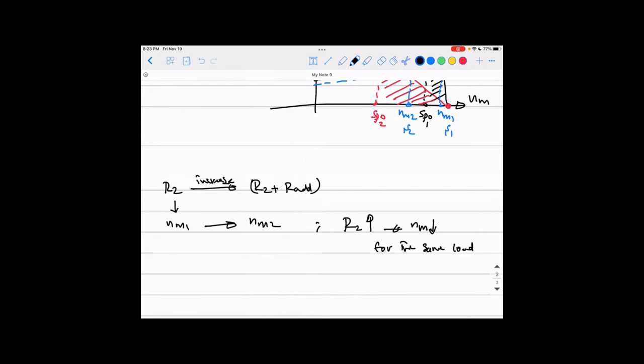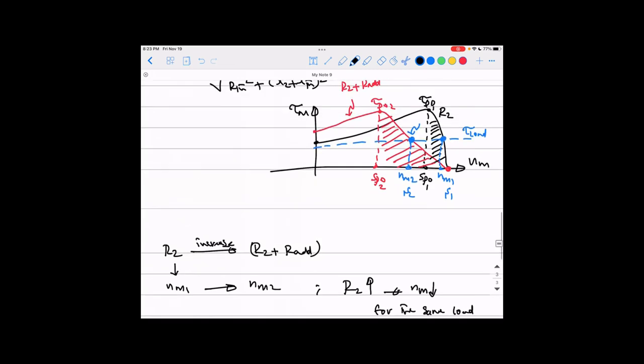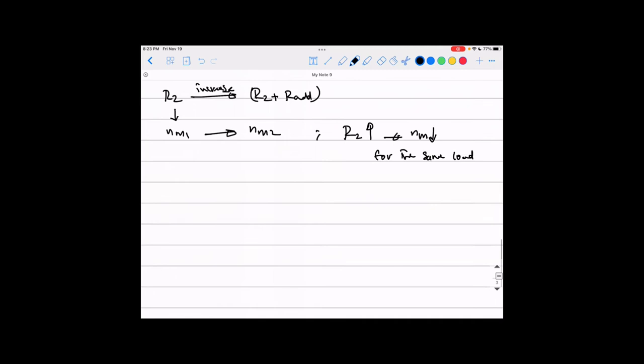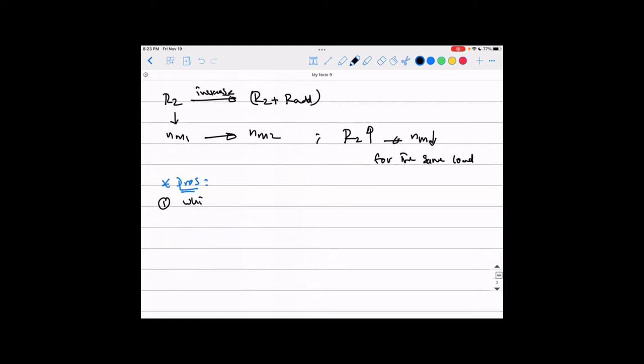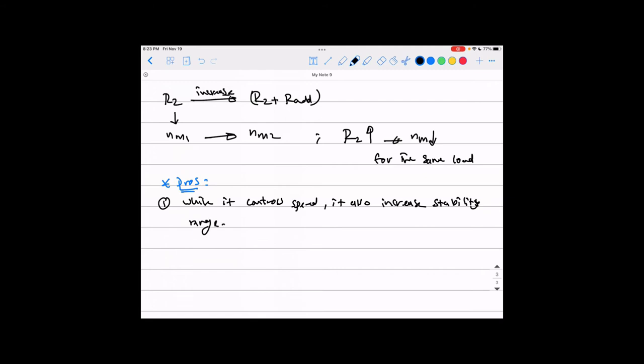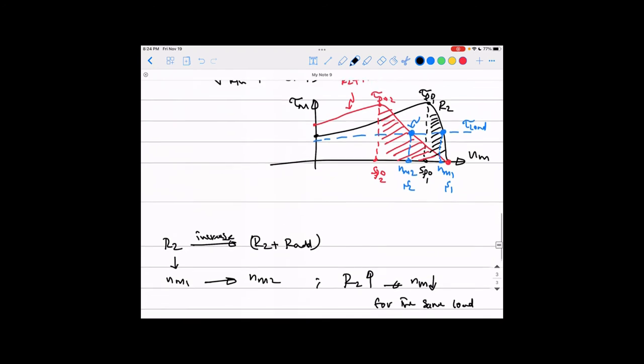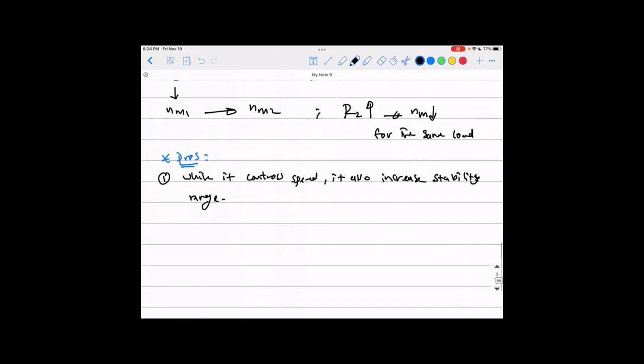With increasing R2 the speed has been reduced for the same load. That is the whole point of this method: add more resistance to the rotor winding and the speed drops down. Now let's talk about the pros and cons of this method — adding resistance to the rotor circuit.